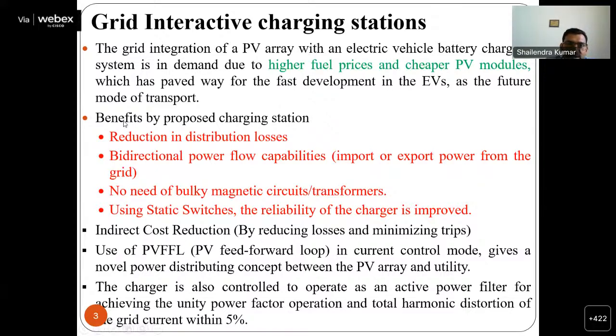What are the other benefits of the proposed charging station? Reduction in distribution losses, as we are compensating these losses as well as providing reactive power compensation from the converter, so distribution losses are reduced.